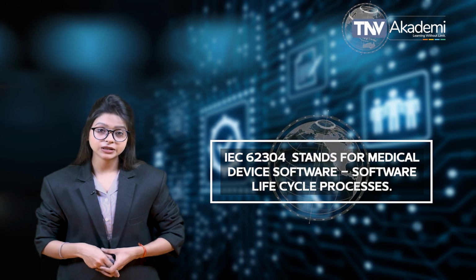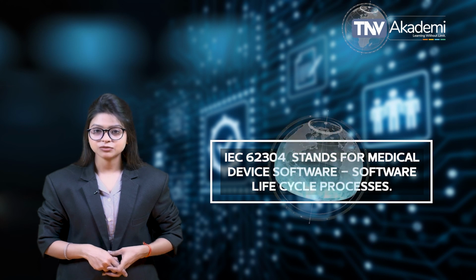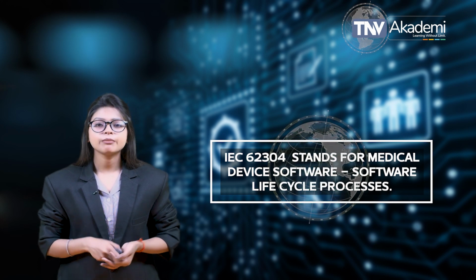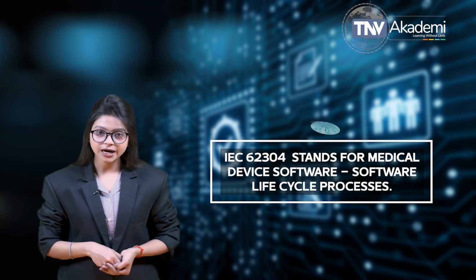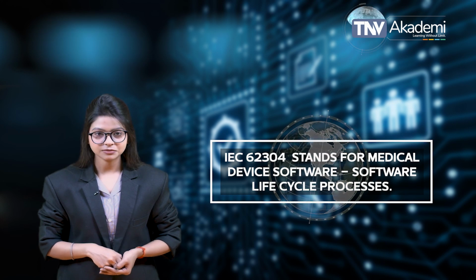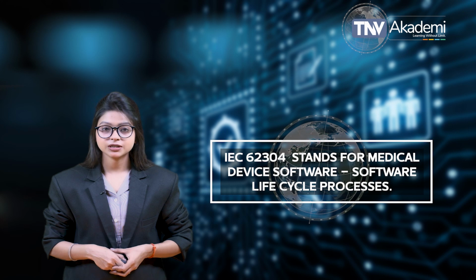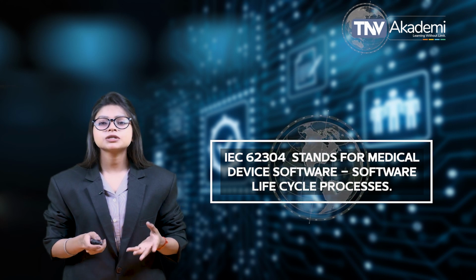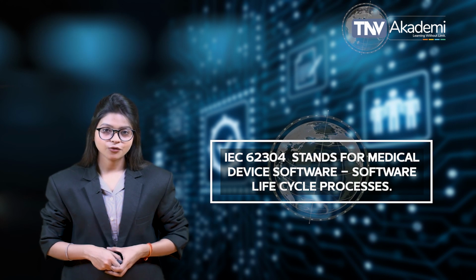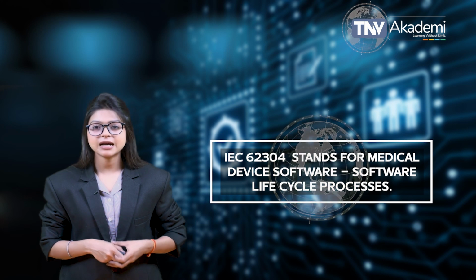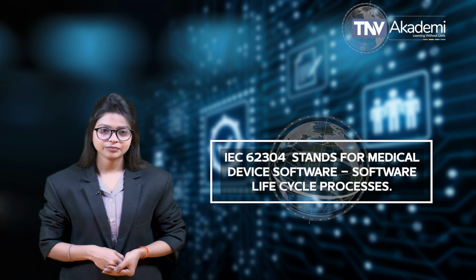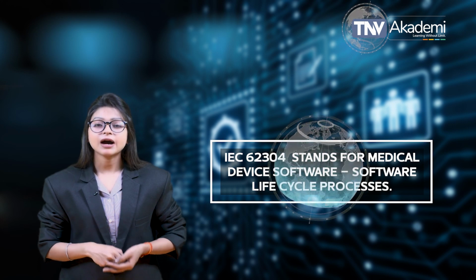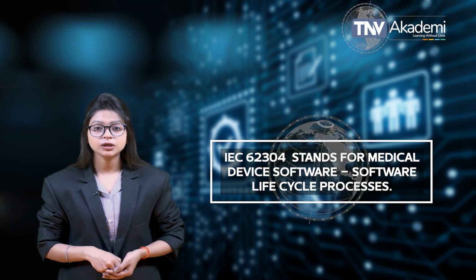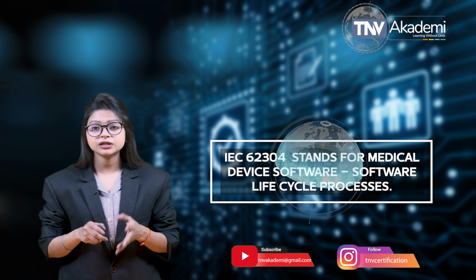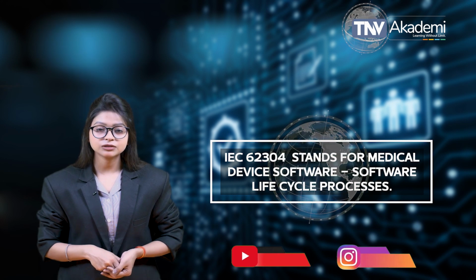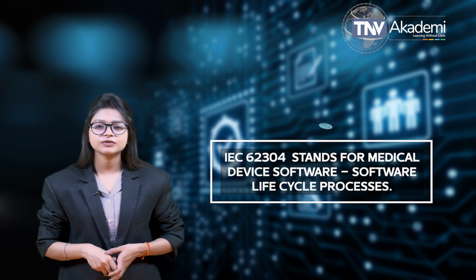When manufacturers build software that either functions as a medical device, SaMD, or that is to be incorporated into a medical device, SiMD, the stakes are high and therefore clear and high standards are needed. Every caution is needed to ensure the safety of patients and efficiency of medical device software used in patient care. IEC 62304 is one of the standards that provides guardrails that enhance the quality of medical device software reaching patients. The underlying principles of IEC 62304 are rigorous planning through documentation, testing, and verification of everything, and finally, traceability, a transparent mechanism to verify compliance of all parts of the standard.